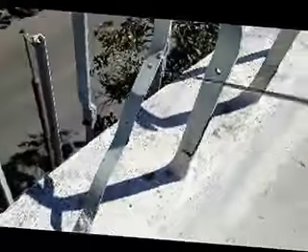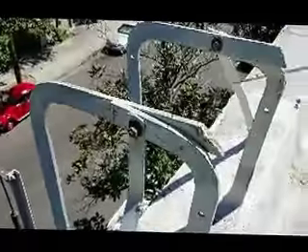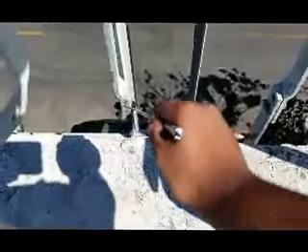As you can see, we have structural support angles here connected by hex head bolts, which is good, but we want to go ahead and silicone shut every connection so we prevent water accumulation and penetration. We have a fixed ladder punched through. That's how we get up here. I just climbed up here, so had no problems climbing it. Apparently this portion of the escape system has been maintained in the past, so we don't know how long, but it's been maintained because we see some rebolting taking place. They swapped it out, took out the old one, and introduced a new one.